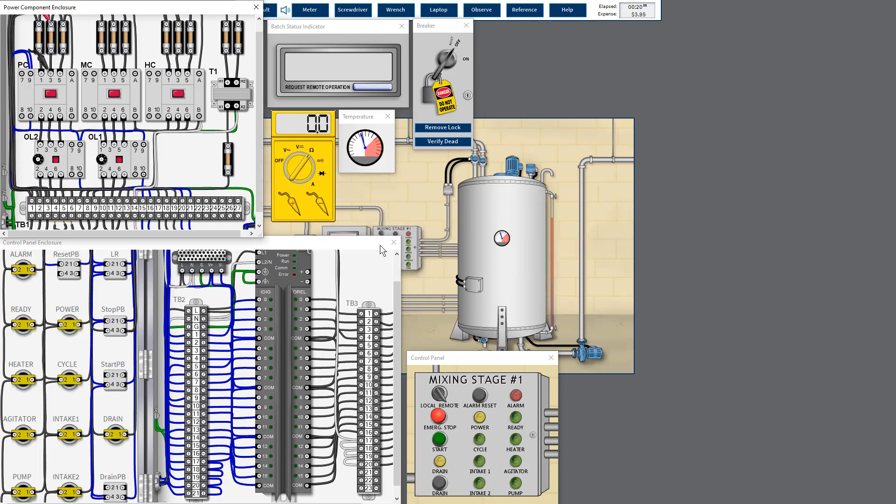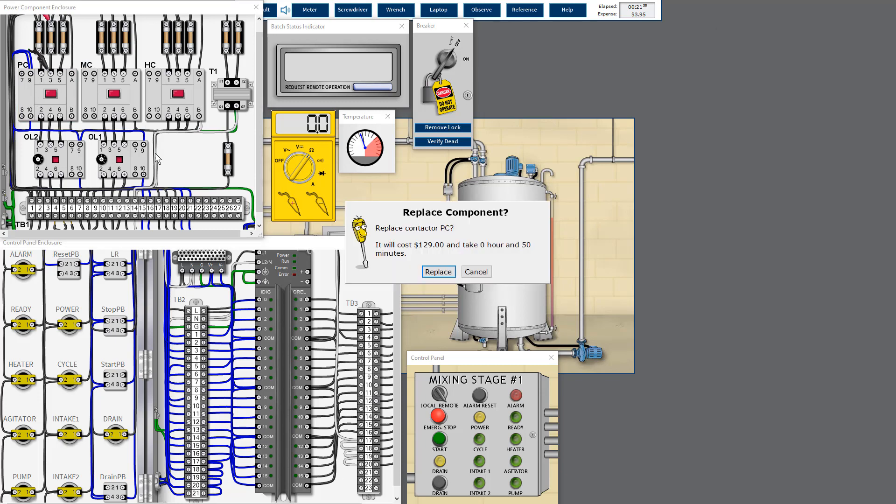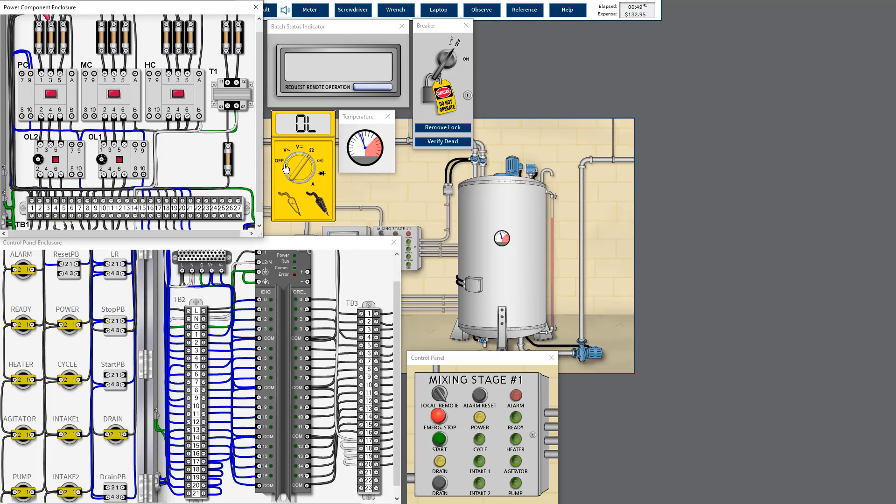New fuse. As what we see just now, we have two phase open, one at the fuse, one at the contactor. That's why under these circumstances there is not enough torque to drive the load. That's why the motor is not running, the pump is not running, because the motor do not pull in enough current to generate high torque to turn the load such as pump, agitator, leaf, conveyor belt, etc. Because of this one it don't pull the current and there's no over current and the overload relay will not be overheated and trip. That's why the overload relay will not trip. Okay, so this contactor we need to replace.